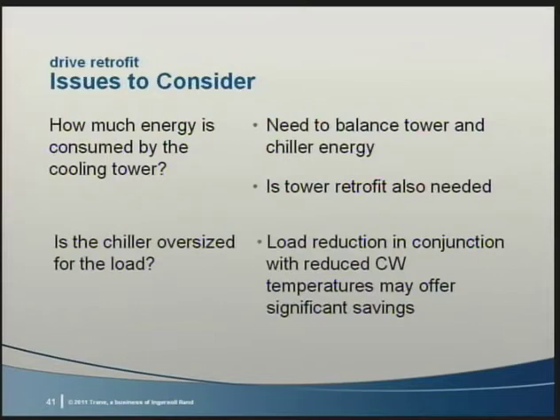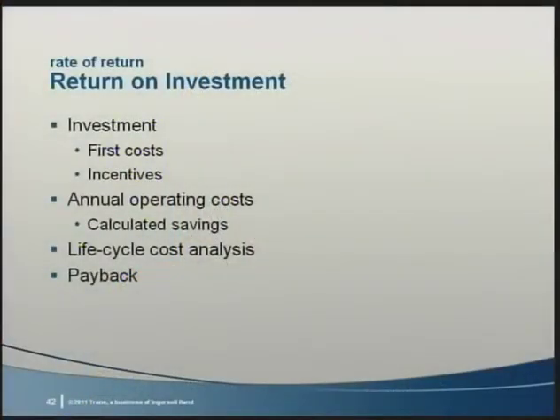Finally, if the chiller is oversized for the load, this load reduction in tandem with the lower condenser water temperatures may offer significant savings. As Susanna pointed out earlier, removing false loads and accounting for building improvements should not be overlooked. Upgrading your existing chiller to improve energy efficiency, while a noble cause, still needs to make financial sense for your organization. You must consider the first cost, which are often reduced by incentives, to the predicted energy savings to determine your return on investment. Life cycle costs should not be overlooked either. The return on investment must meet your organization's internal requirements and goals.